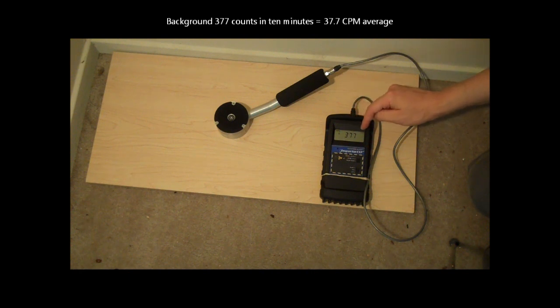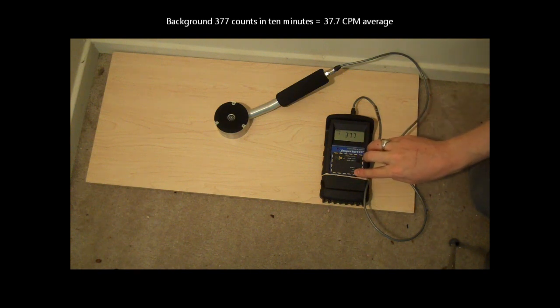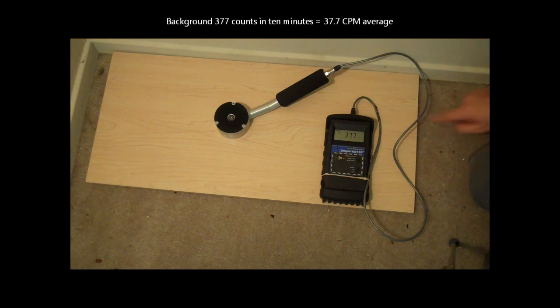Alrighty. Now, as you can see, we have a background count of 377 counts in 10 minutes. 377 divided by 10 is 37.7. So our average background count is 37.7 counts per minute. Let me cut the sound on so you can hear. 37.7. Here is an iPad.